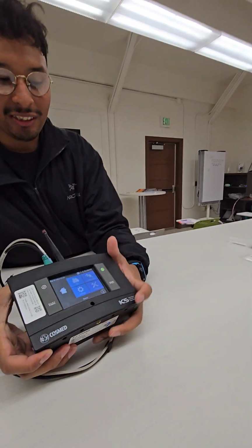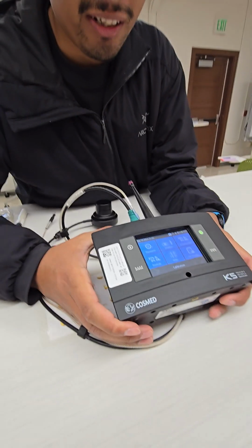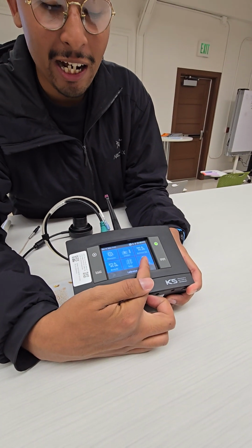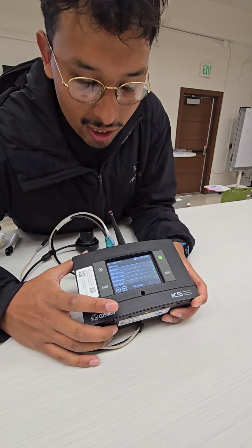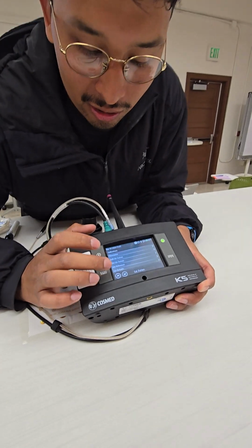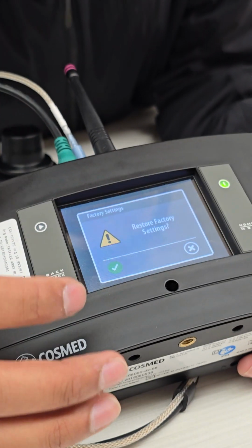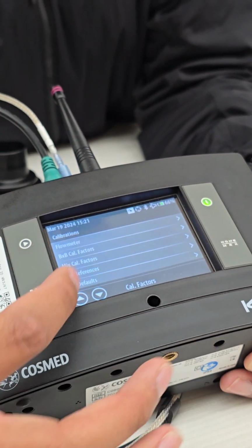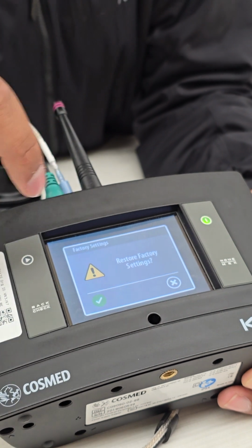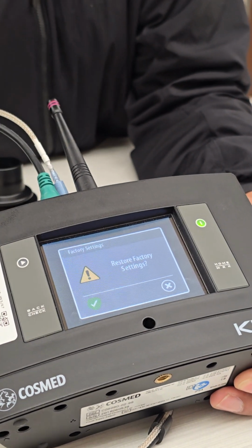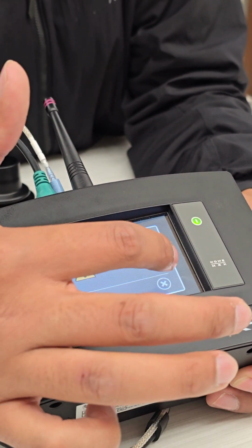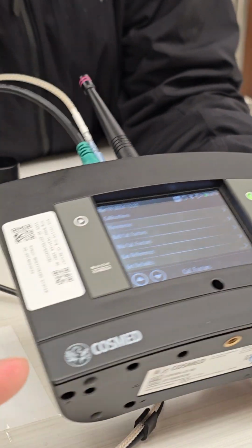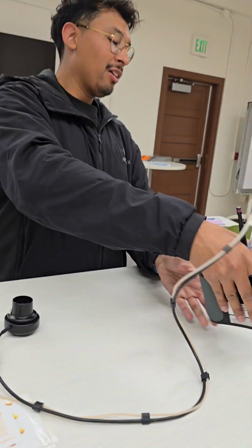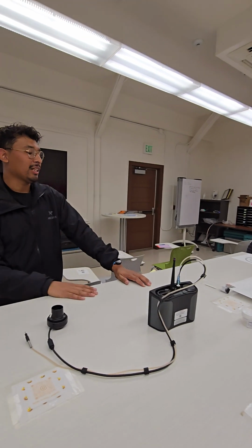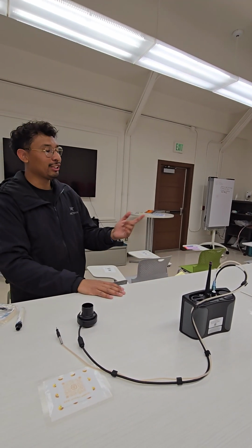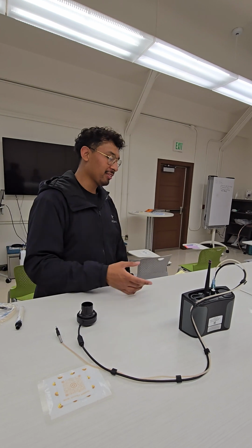Into calibration, and then there's this little... It's called calibration factors. From here, you go into, I think it's set defaults. Yeah. So set defaults, and then it'll confirm that you want to restore the factory settings, and you just click check, and that's pretty much it. And you don't have to recalibrate the flow meter at this point? Technically, yes. Since we just restored the factory settings, we're supposed to.